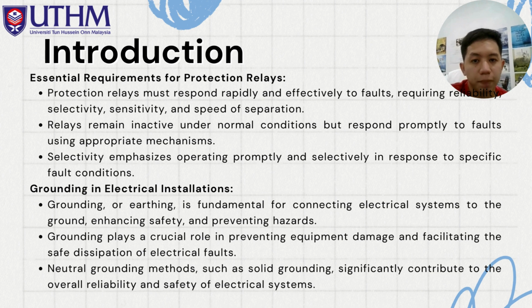The protection relay must respond rapidly and effectively to faults, requiring reliability, selectivity, sensitivity, and speed of separation. Relays remain inactive under normal conditions but respond promptly to faults using appropriate mechanisms. Selectivity emphasizes operating promptly and selectively in response to specific fault conditions. Grounding or earthing is fundamental for connecting an electrical system to ground, enhancing safety, and preventing hazards. Grounding plays a crucial role in preventing equipment damage and facilitating the safe dissipation of electric faults. Neutral grounding methods such as solid grounding significantly contribute to the overall reliability and safety of electrical systems.